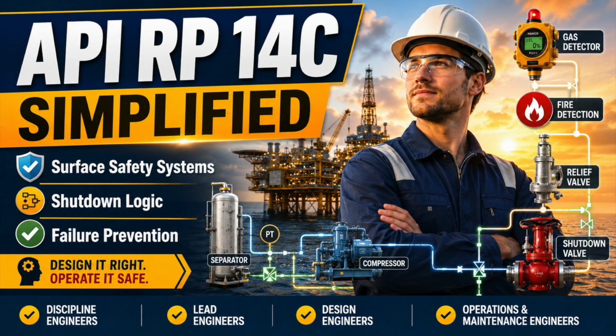The pipeline is isolated, but a branch between the shutdown valve and check valve can still be backfed. The separator trips on high level, but the liquid already moving through the piping reaches the compressor scrubber before the valve fully closes. Safety boundaries must follow pressure, flow, inventory, and energy, not equipment tag numbers. For every component, identify the undesirable events.